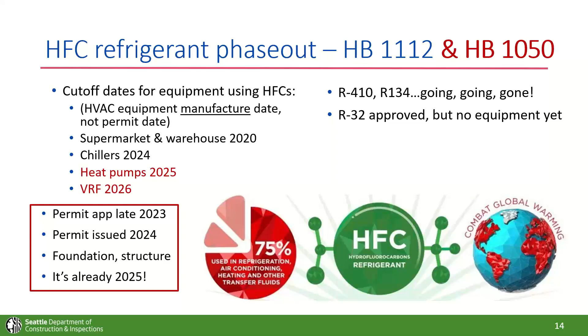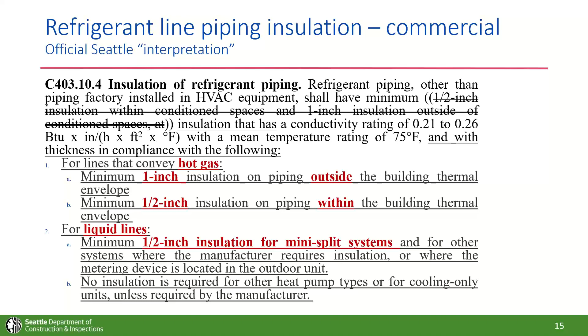So plan accordingly. One small thing - I kind of muffed the refrigerant piping earlier, so as an interpretation, we're saying the hot gas line on refrigerant piping would be one inch thick outside the building and a half inch inside, and for the liquid lines it'd be a half inch for mini splits or where the manufacturer wants that, and otherwise none for those liquid lines unless they ask for them.